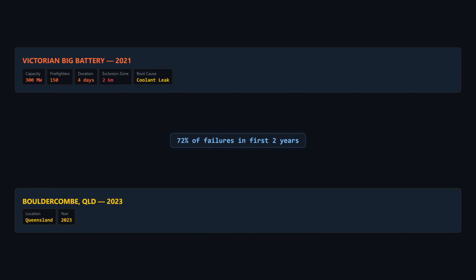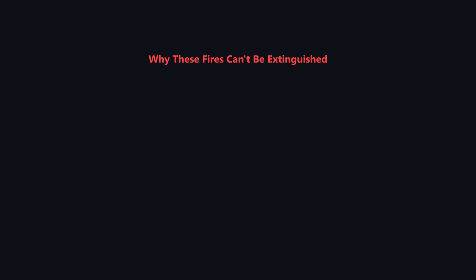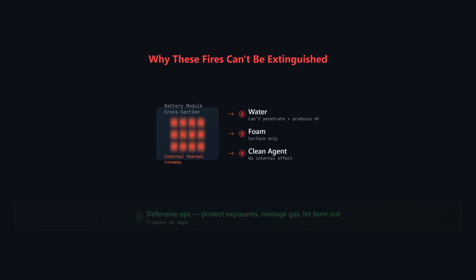The pattern is clear. 72% of BESS failures occur during commissioning or the first 2 years. There is currently no proven suppression system that can extinguish thermal runaway inside a battery module. Water cools the exterior but can't penetrate sealed cell casings. Worse, water reacting with lithium compounds produces more hydrogen fluoride. Foam and clean agents suppress surface flames but don't stop the internal chain reaction. The battery provides its own oxidizer. The most effective strategy is defensive. Protect surrounding assets, manage toxic gas exposure, and let the battery burn itself out. This can take hours to days. Fire agencies worldwide agree on this approach.